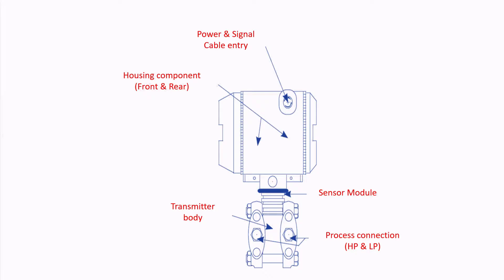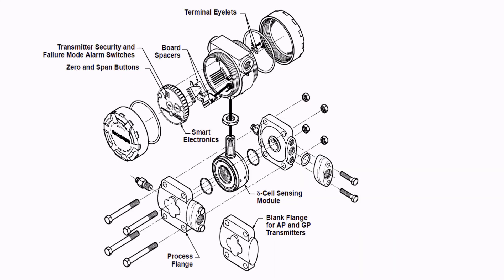This is the general arrangement of a transmitter — this is a differential pressure transmitter. You can see the conduit area at the top for power and signal cable entry. We also have housing components front and rear. As I told earlier, there are two openings, and in the central part you will see a sensor module that integrates the sensor and electronic components. In the bottom front you can see the process connection — it has both the high pressure and low pressure process connection flanges.